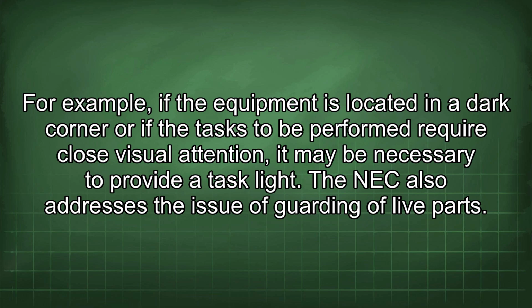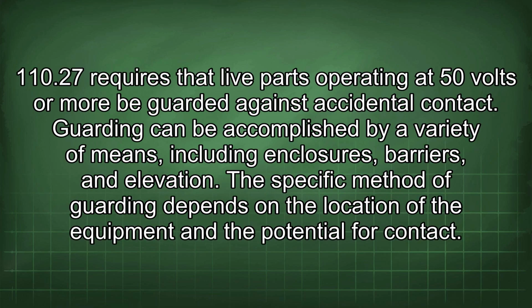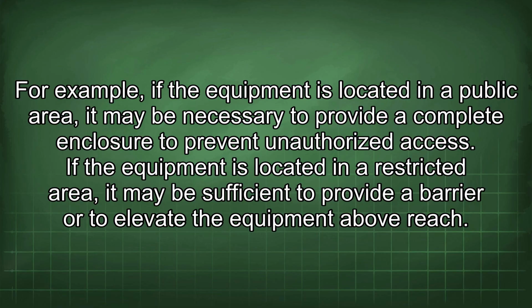The NEC also addresses the issue of guarding of live parts. 110.27 requires that live parts operating at 50 volts or more be guarded against accidental contact. Guarding can be accomplished by a variety of means, including enclosures, barriers, and elevation. The specific method of guarding depends on the location of the equipment and the potential for contact. For example, if the equipment is located in a public area, it may be necessary to provide a complete enclosure to prevent unauthorized access. If the equipment is located in a restricted area, it may be sufficient to provide a barrier or to elevate the equipment above reach.